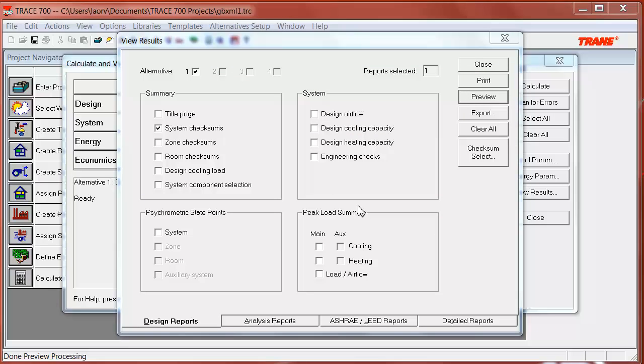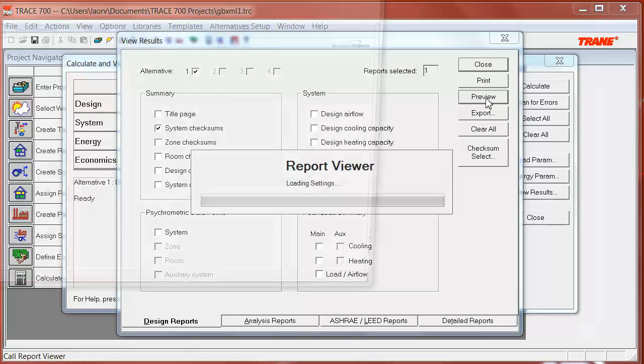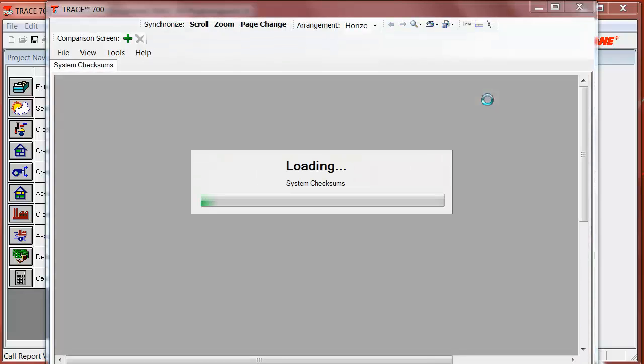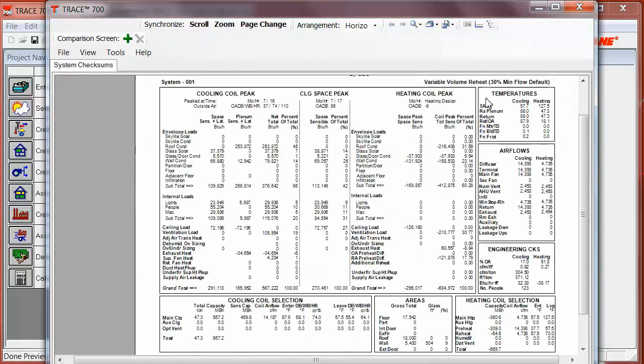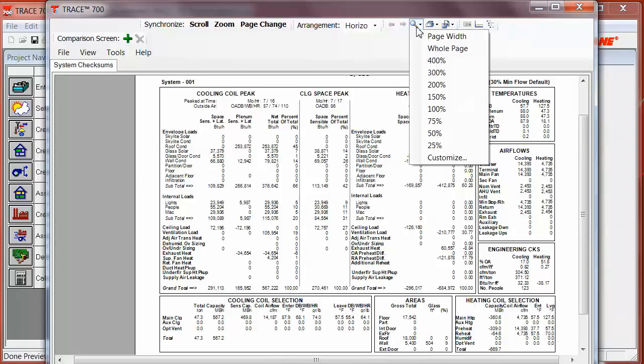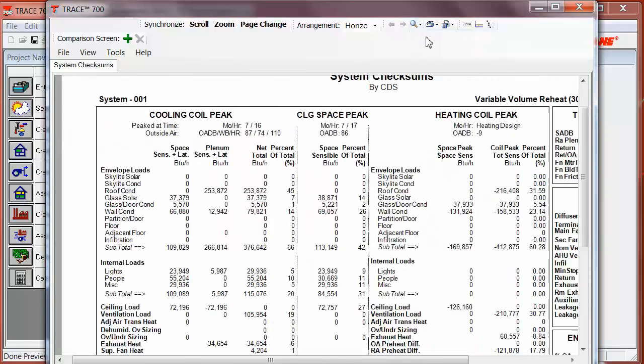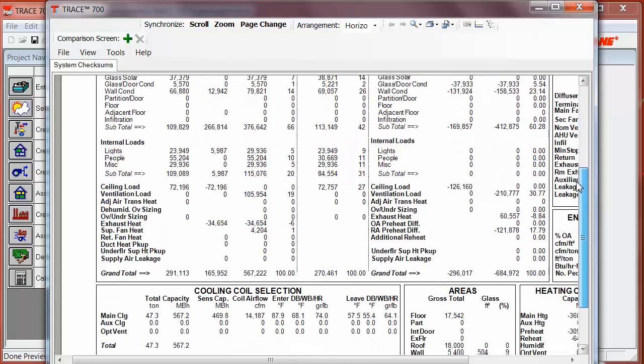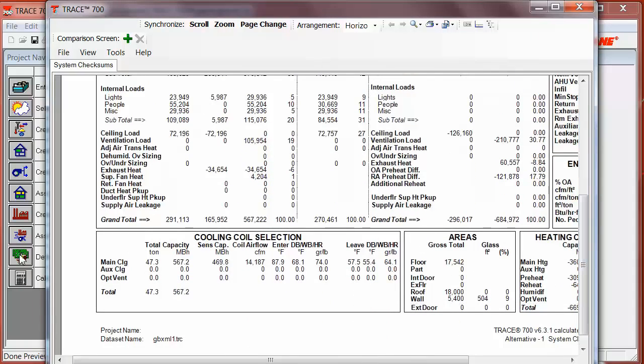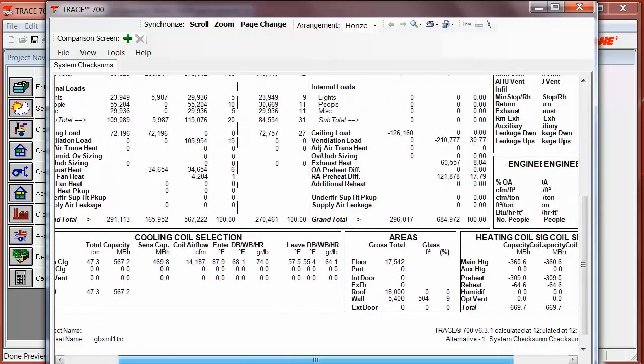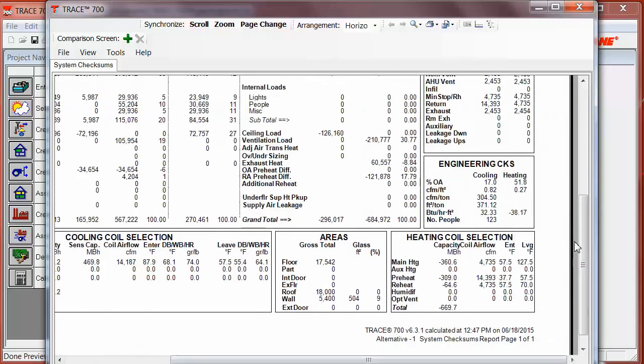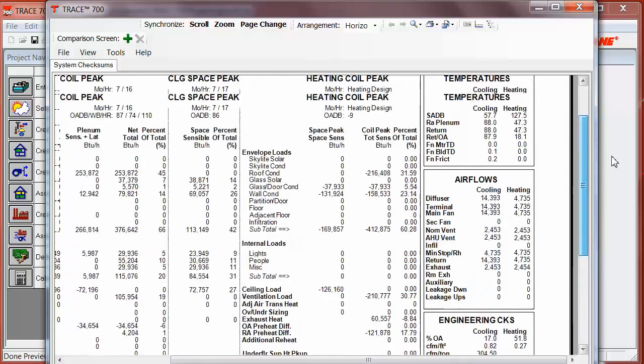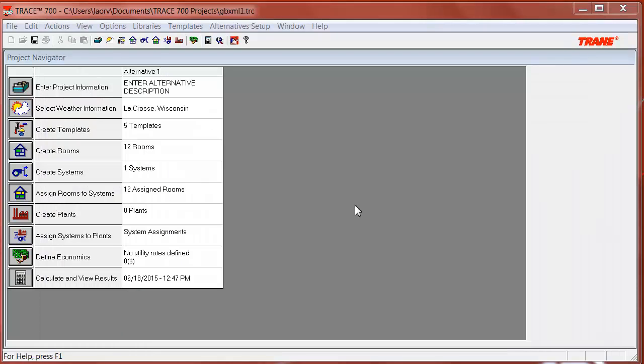I can verify my inputs and outputs through some reports. Here, I'm going to take a look at the system checksum report. Remember that the system checksum report is a system page overview of the cooling and heating loads, and also the design information, so you can use it to check the load design calculation. Here, I can see the cooling coil peak, the cooling coil selection, heating coil selection, and also the air flows.